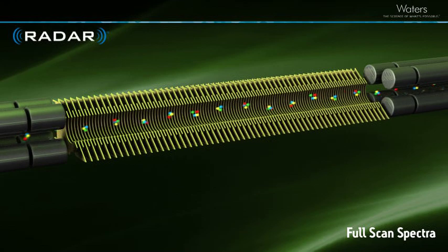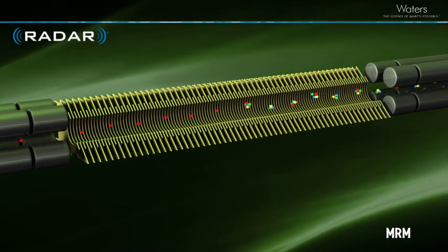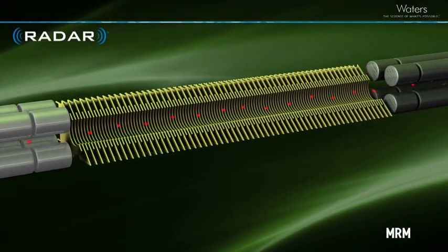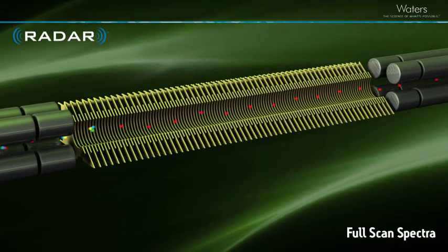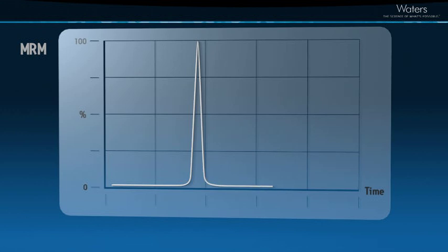In Radar mode, the Xevo TQS rapidly alternates between MRM and full scan MS acquisition modes. You can track your target analytes with precision in MRM mode while at the same time scanning the background for all other components.